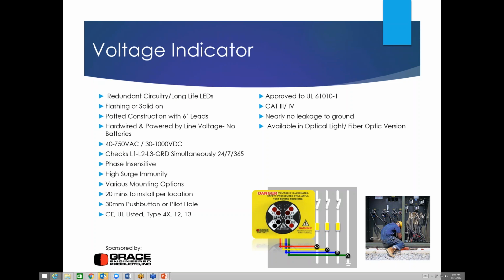And the voltage indicator here is really being used for anybody walking by or an operator to simply look over and see that there's a problem or a change. And really what we're trying to do is to get them to pick up the phone and call the electrical group or the maintenance group. A couple other things: obviously, these devices are UL listed. They are approved to UL 61010-1, Cat 3 and Cat 4 rated, and available in an optical light or fiber optic version for those of you who have strict policies regarding any types of voltage on the door.